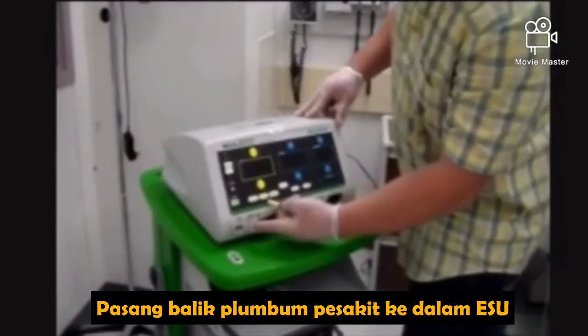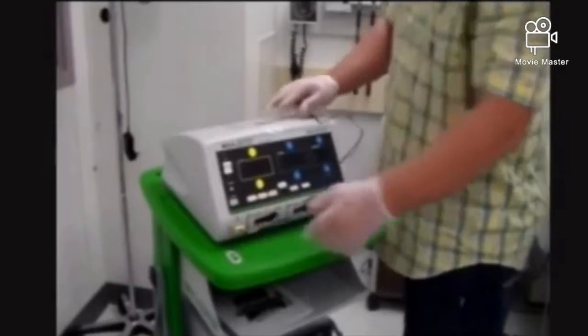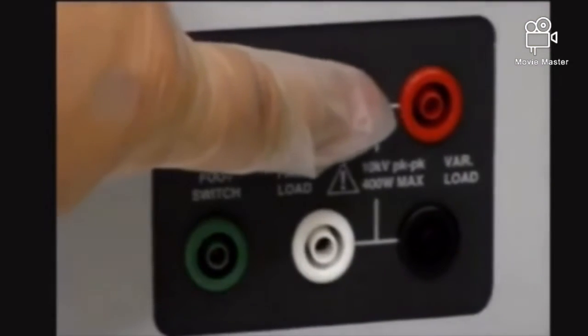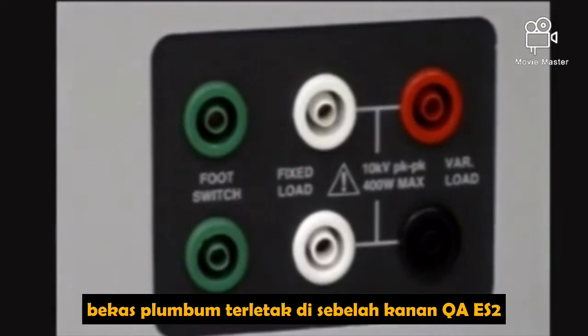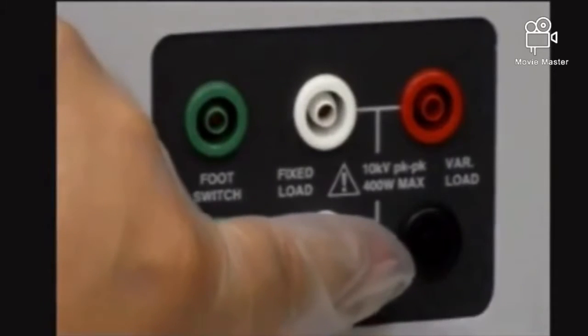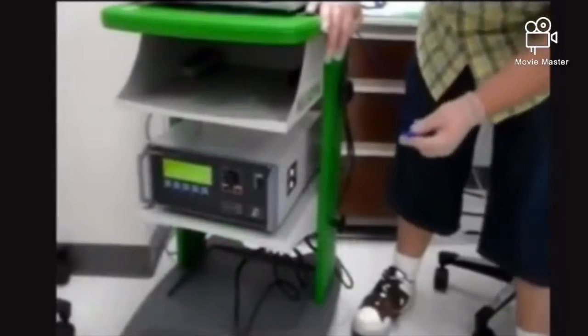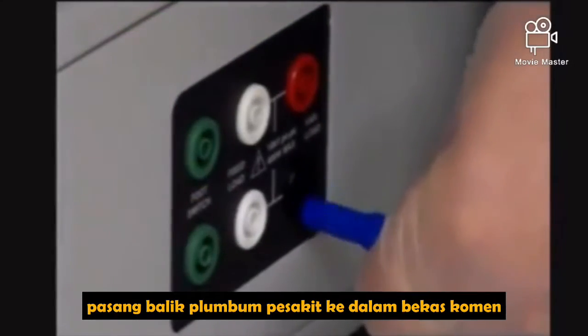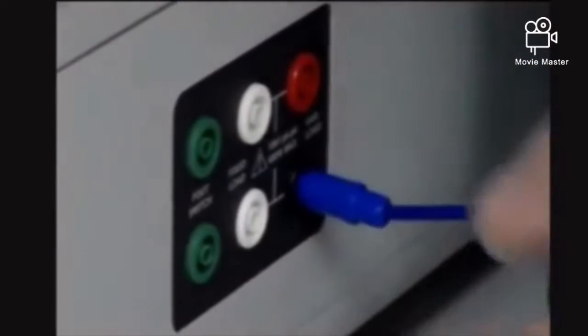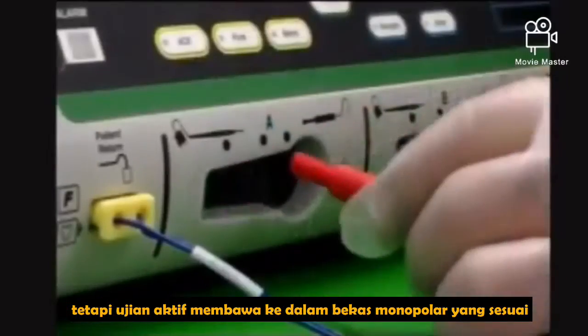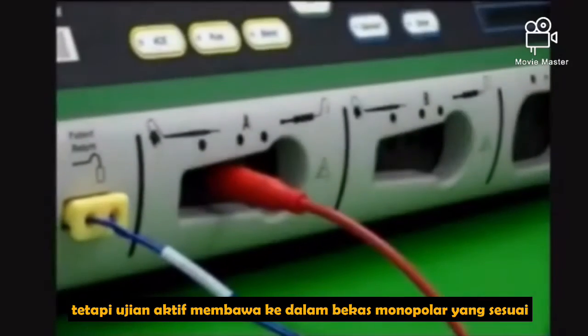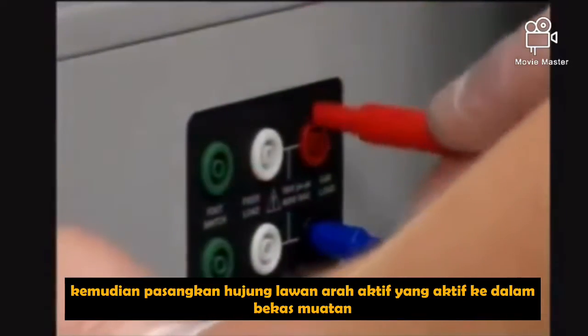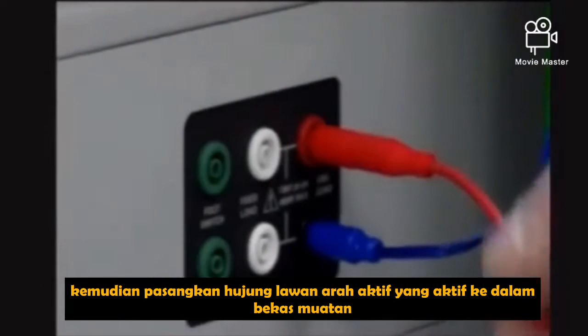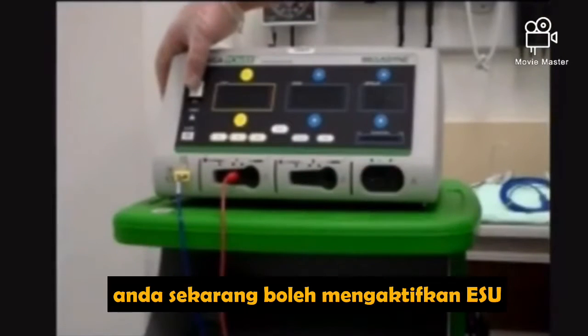Install the patient return lead into the ESU. The lead receptacles are located on the right side of the QA-ES2. Install the patient return lead into the common receptacle. Plug the active test lead into the appropriate monopolar receptacle. Then plug the opposite end of the active test lead into the load receptacle. You may now power the ESU.